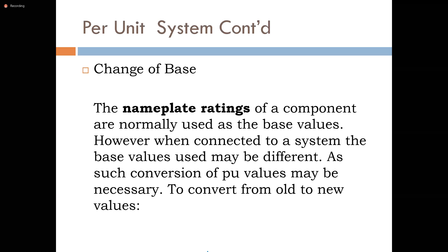So when I make a transformer, if the reactance of the transformer is 5 ohms, and I put it in a system where the impedance base is 20 ohms, it means that the per unit would now be 0.25. If I take out that same transformer and put it in a system where the base value is 100, it still has 5 ohms. But because the base is now 100, it means that the per unit reactance will now fall to 0.05. Are you with me? So the actual value can't change. If I take up the transformer from Jamaica and carry it to Mexico, it's the same transformer, it's the same 5 ohms. But when I put it in a different system with a different base, the per unit value will change.